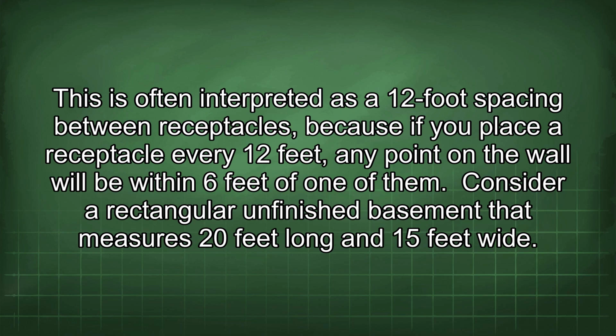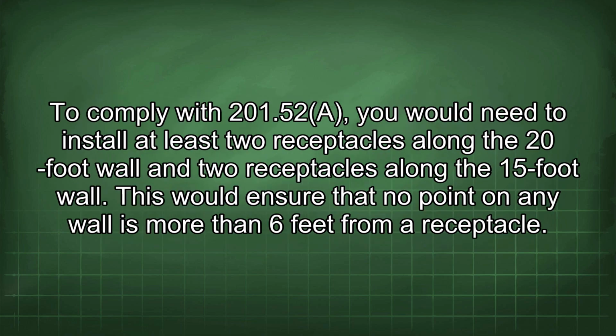Consider a rectangular unfinished basement that measures 20 feet long and 15 feet wide. To comply with 201.52(a), you would need to install at least 2 receptacles along the 20-foot wall and 2 receptacles along the 15-foot wall.